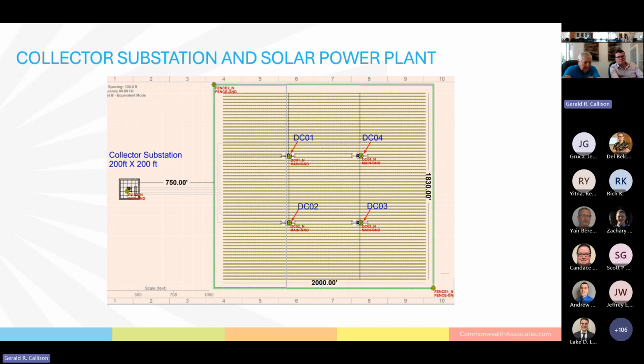Okay, so we look at what the collector substation and the solar plant facilities look like. The solar plant is essentially a 2,000 foot by 1,830 foot footprint. There's lots of solar panels in this plant. You have 4 places where you have inverters, and they're described as DC 01 through 04. The collector station is a 200 by 200 foot ground grid, and it's located fence to fence approximately 750 foot apart.